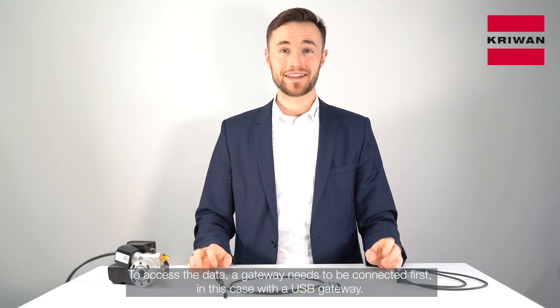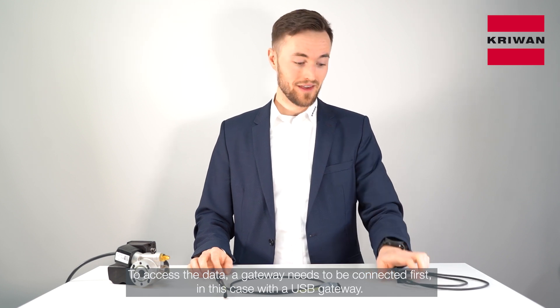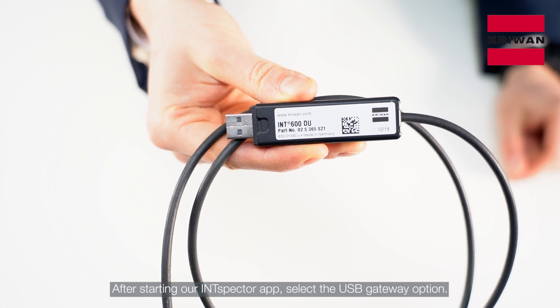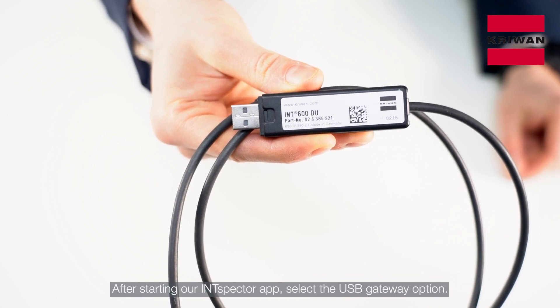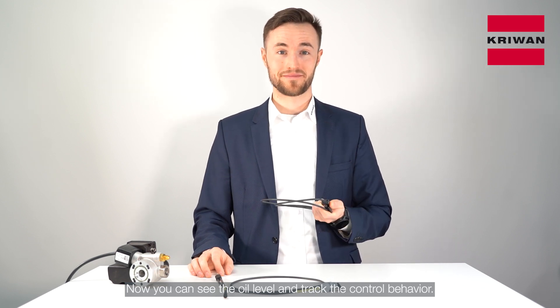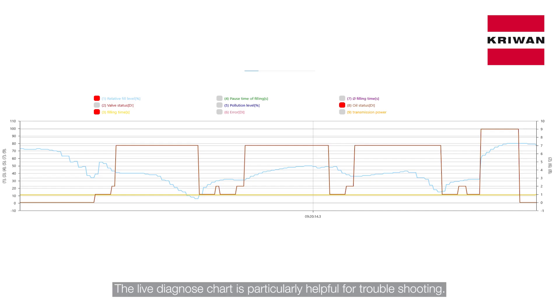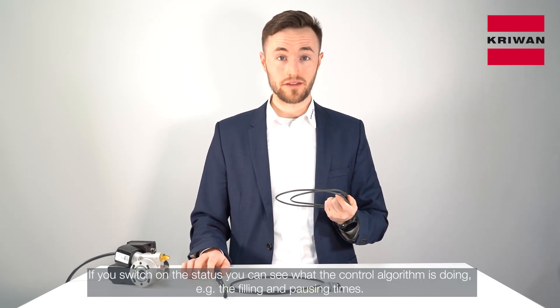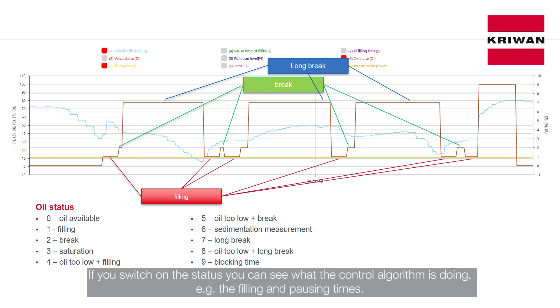To access the data, a gateway needs to be connected first — in this case, a USB gateway. After starting our INTspector App, select the USB gateway option. Now you can see the oil level and the control behavior. The Live Diagnose chart is particularly helpful for troubleshooting. All values are shown, recorded and saved in a CSV file on your tablet. If you switch on the status, you can see what the control algorithm is doing — for example, filling and pausing times.